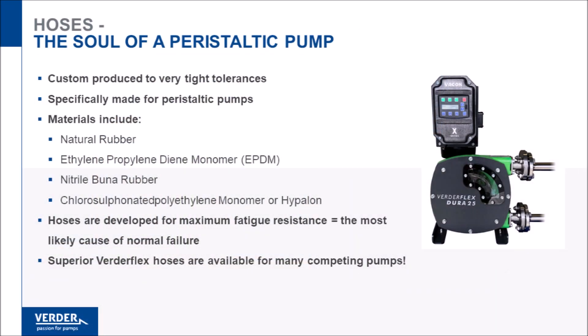Peristaltic pump hoses are made to very tight specifications for maximum working life. Hoses are made in several materials including natural rubber for general application, EPDM for corrosive products, Buna for oil and solvents, and Hypalon for high-strength acid. Verderflex hoses are engineered for maximum fatigue resistance, thus providing longer life. Also, Verderflex hoses are available for many competing hose pump brands.